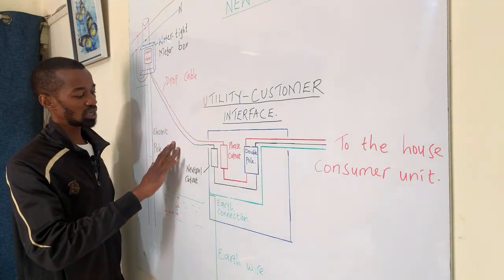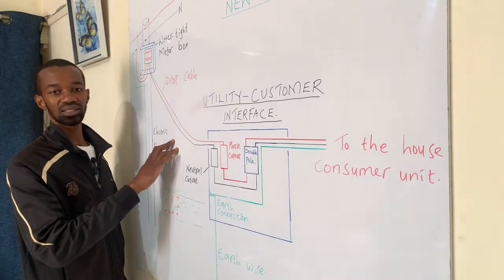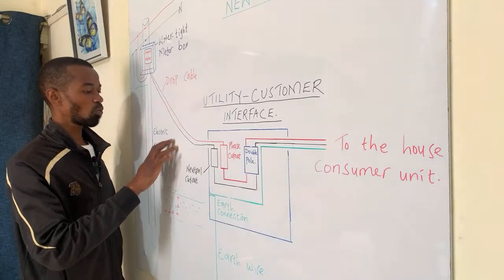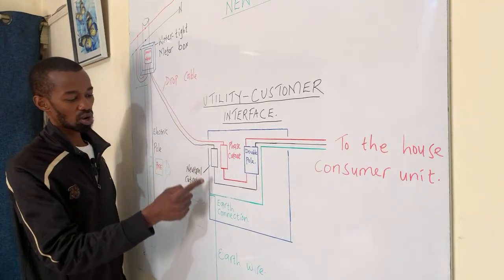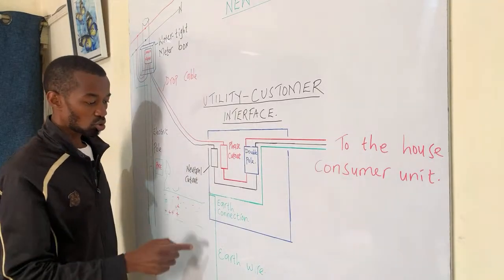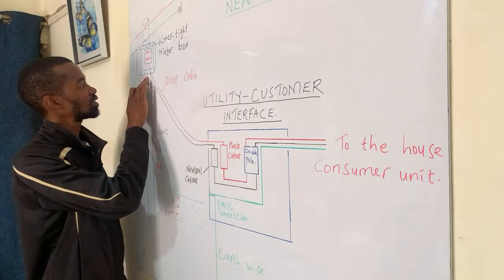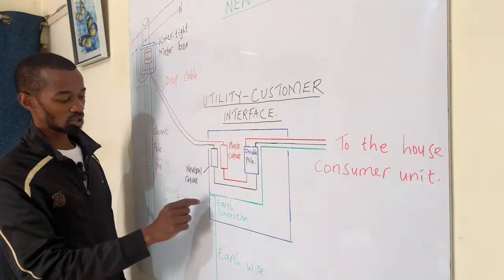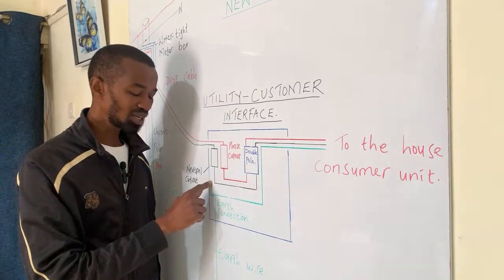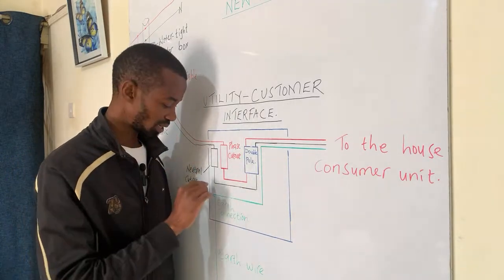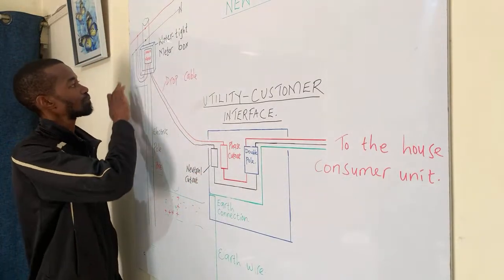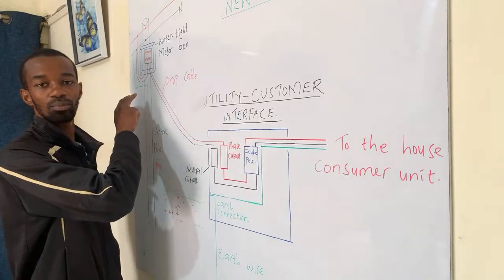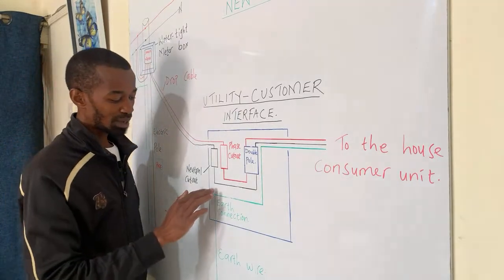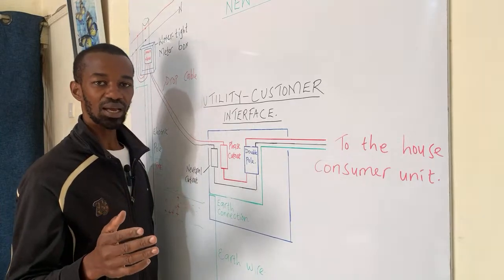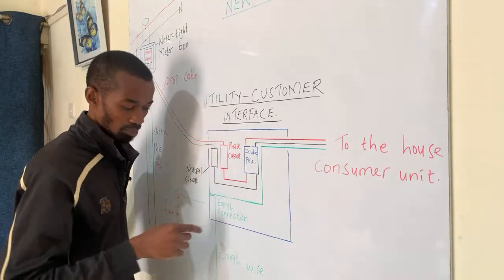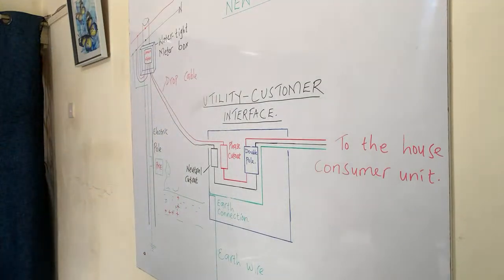That is a topic that we have really been having issues with many electricians online, because my question would be, why again would you need to loop the neutral and the earth? So once this drop cable comes in, if you have the meter mounted at this particular point, you don't need to bond the neutral and the earth again, because already the neutral has been bonded with the earth at the PME. When it comes to this particular point, if the meter is now in the meter box, for instance, let me give you an example here.